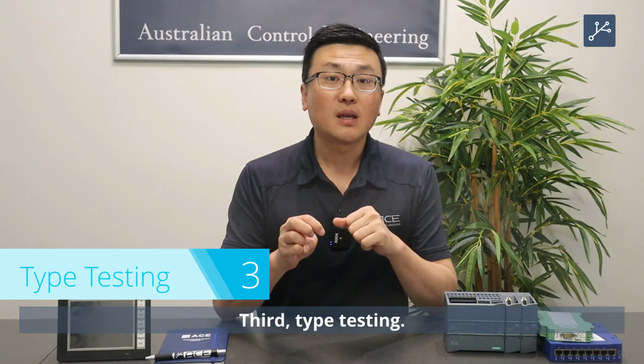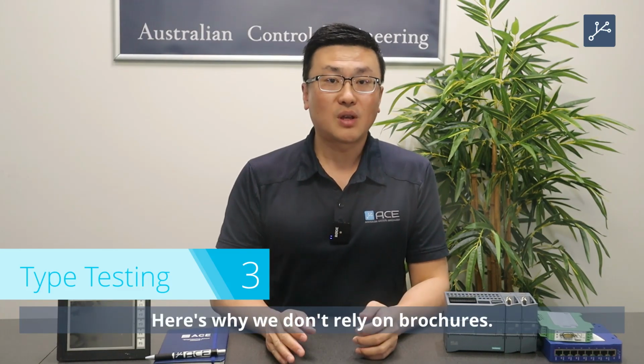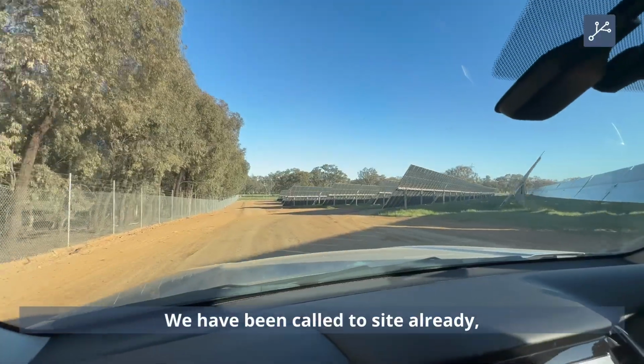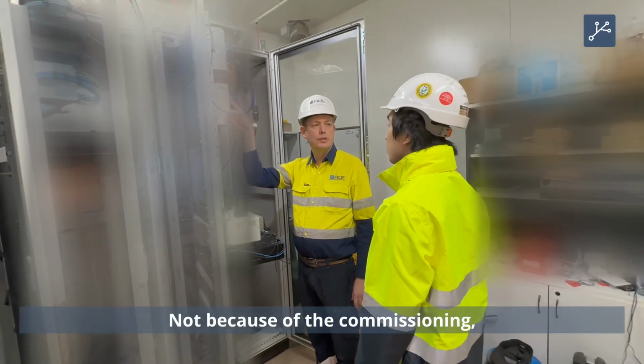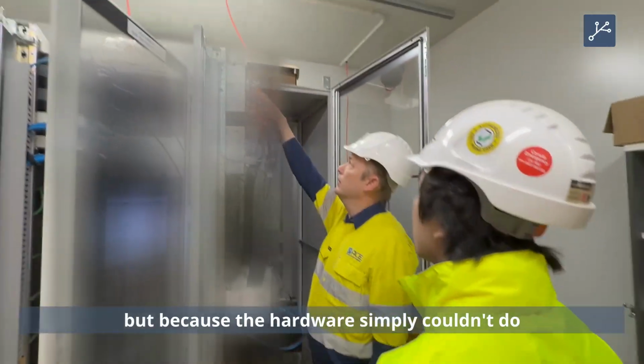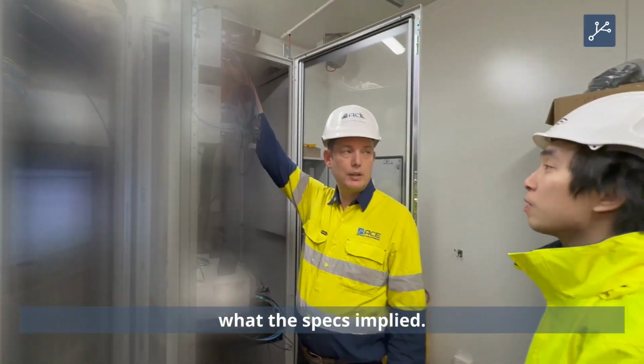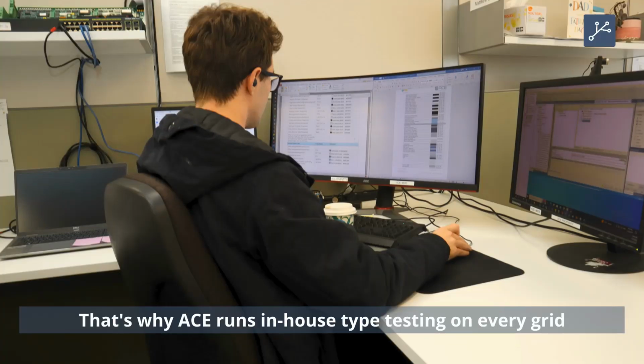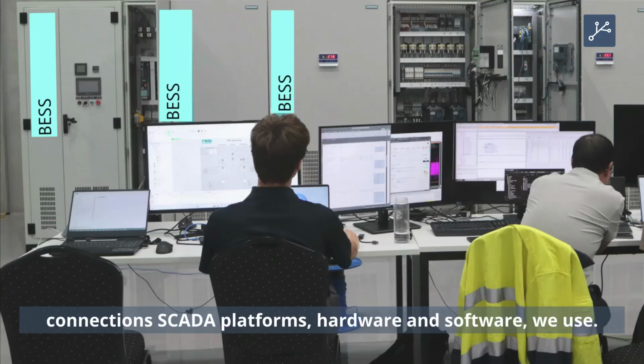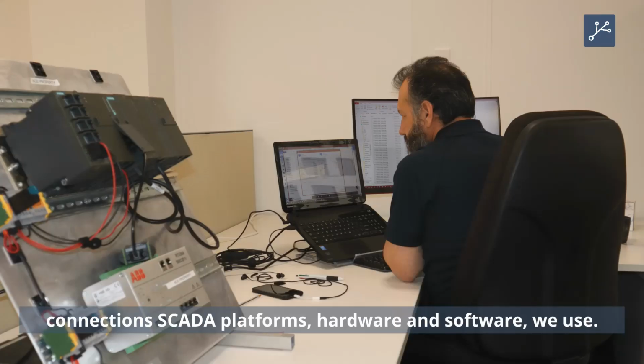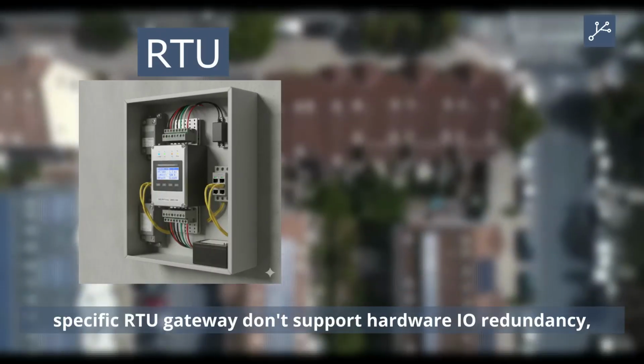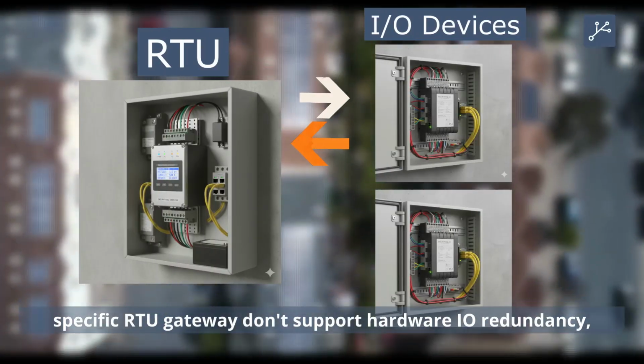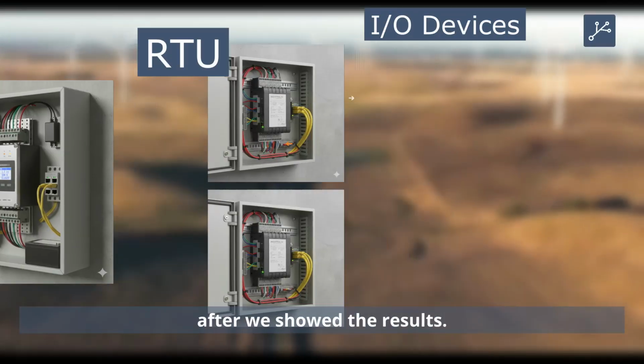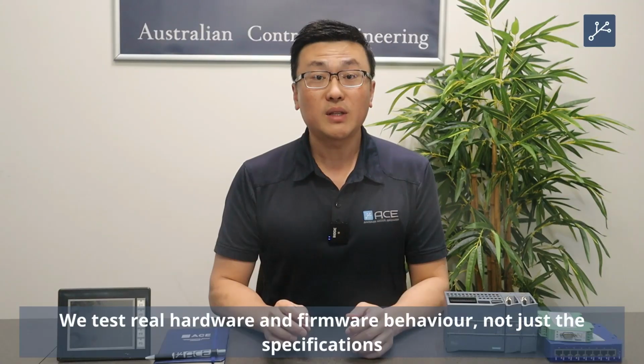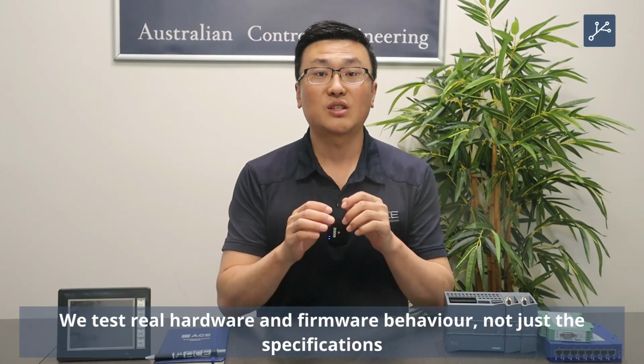Third, type testing. Here's why we don't rely on brochures. We have been called to site already in SAT, where the redundancy test was failing. Not because of the commissioning, but because the hardware simply couldn't do what the specs implied. That's why ACE runs in-house type testing on every grid connection SCADA platform's hardware and the software we use. In one recent test, we proved a specific RTU gateway doesn't support hardware I/O redundancy, and the vendor only confirmed it after we showed the results. We test real hardware and firmware behavior, not just the specifications.